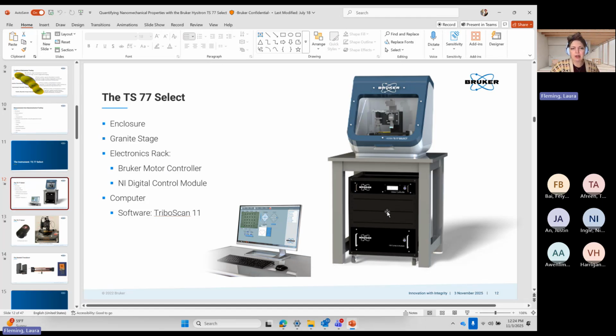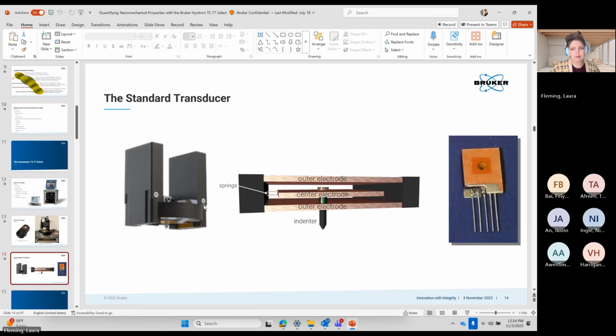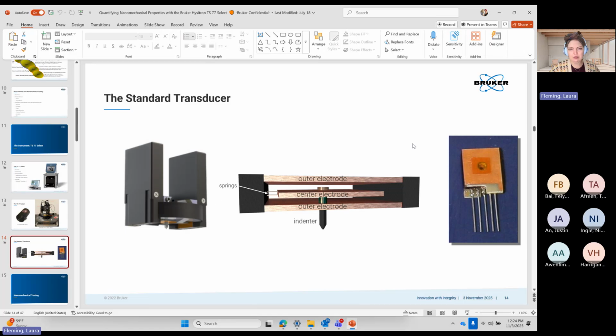Below that, you have the electronics rack, which comes with a Bruker motor controller that drives your X, Y, and Z stages, and your NI control module. That's the brain of the instrument. It has your DAC cards, it talks to the software, it takes your data. That talks to your computer, which has the software called Triboscan 11. Here's a better view of that standard transducer, where you have that outer electrode and the center electrodes with your indenter directly connected. And here's what it looks like.